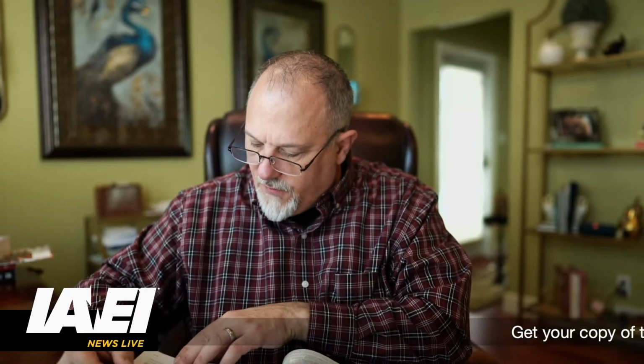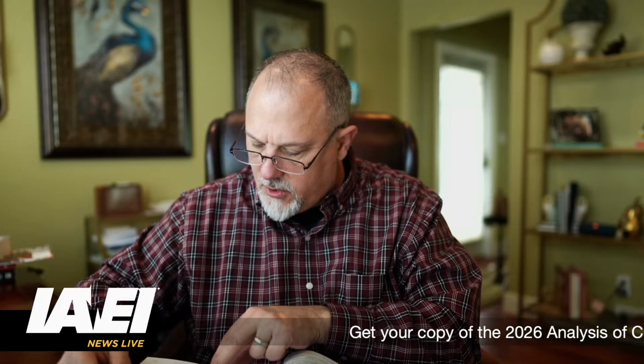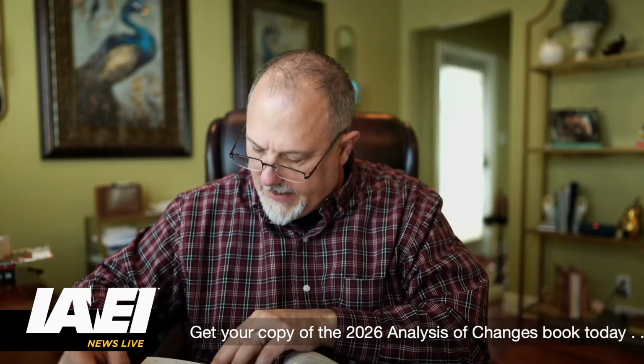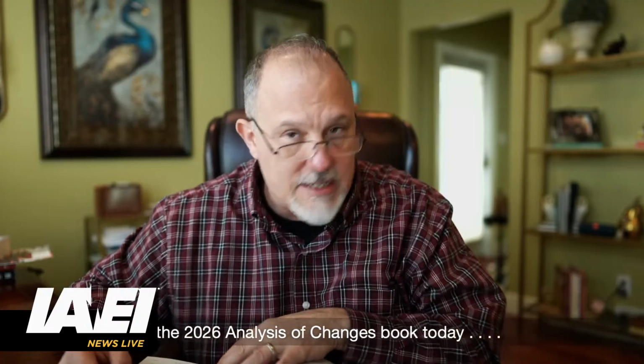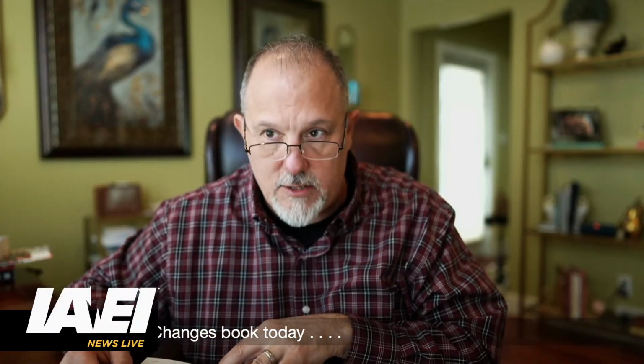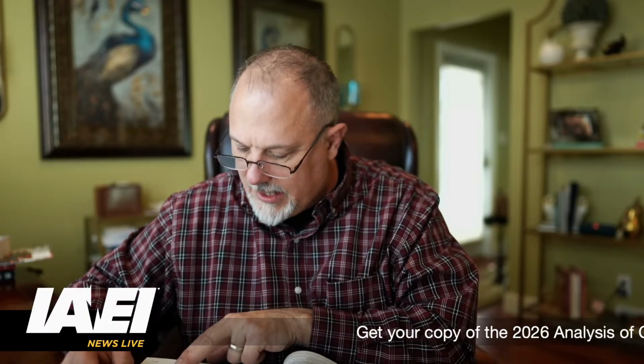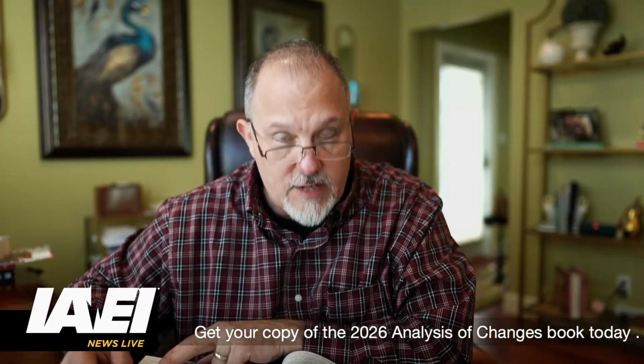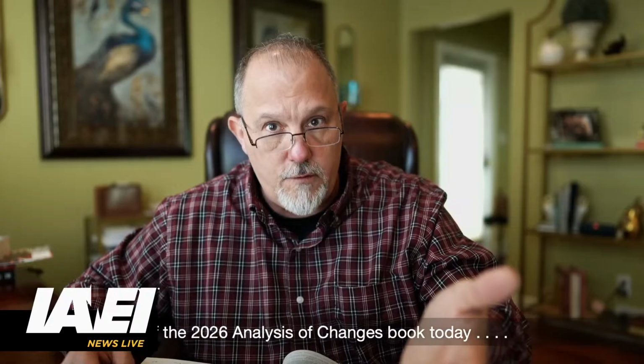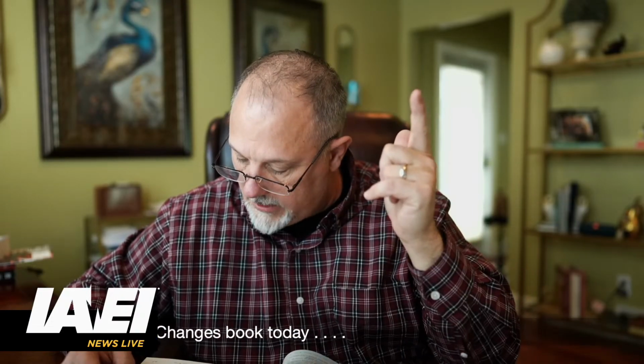It's all 125 volt through 250 volt receptacles that are in these identified locations. So it doesn't matter the ampere rating—it could be a 15, a 20, a 10, a 60, an 80, 100, whatever. It's all receptacles installed; it's got to be 125 volt through 250 volt. So that covers the stove receptacles, things like that.